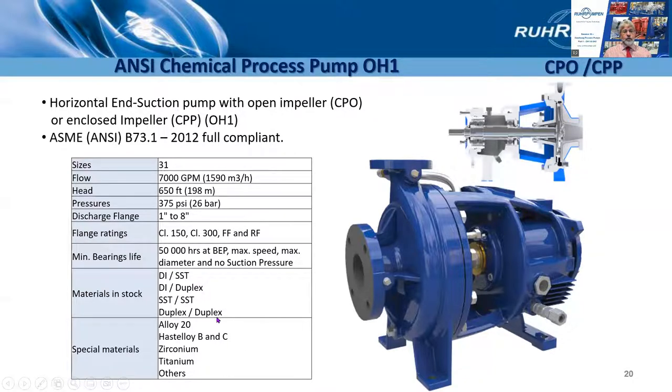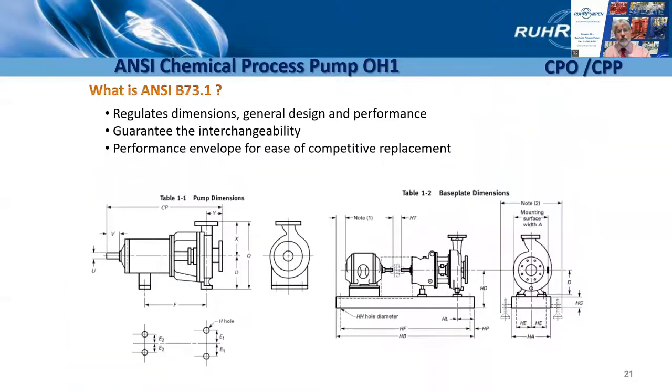These are the materials that we routinely stock. We keep supposedly all our sizes, one of each of these sizes, permanently in stock, so for instant delivery. And these are materials that are available if you've got a little more time. Now, as we said earlier, the dimensions of the pump and the base plate are prescribed for the pump sizes within the standard. So any pump of any manufacturer is dimensionally and performance-wise interchangeable with the same size pump from another supplier.